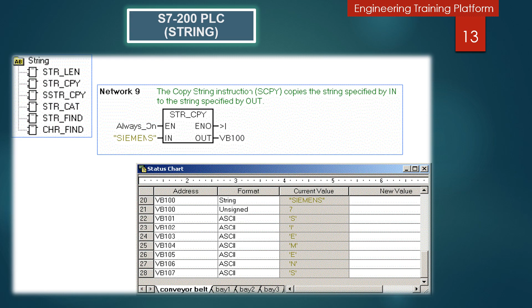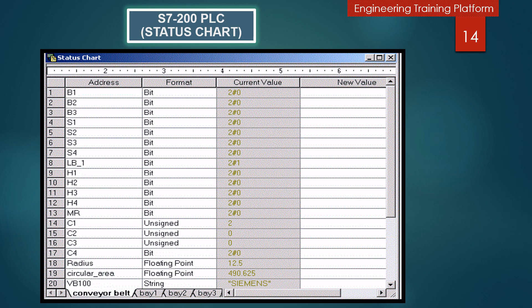For the status chart, after you have downloaded your program into the PLC, you can create one or more status charts to monitor and test the program execution. If the PLC is in run mode, the program is executed consecutively, and you can turn on the chart status so that the status values in the chart are continuously updated. As an alternative, you can use the single read function to make a snapshot of the status values in the chart without having to turn on the status chart. While you are viewing a status chart, you can also put the PLC into stop mode and execute only the first or a specific number of scan cycles in which you monitor the program execution. Please note that you cannot modify your chart when the chart status is turned on. Turn off the status chart if you want to edit the chart.